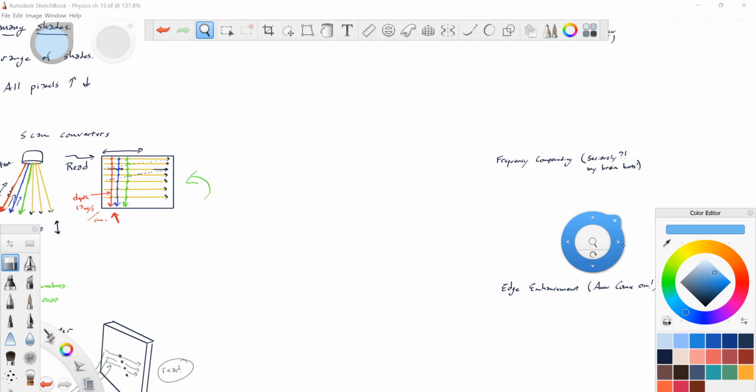Now, here's the thing. When I say theoretically, I have tried this many times on our machines, and perhaps it's just a testament to the quality of the image in the first place. I can't see the difference between read and write magnification on our machines, but theoretically we can. So read magnification uses old data, old as in the data you saved just a second ago. It is post-processing, larger pixel size. No, a pixel is a pixel, but you've changed this.